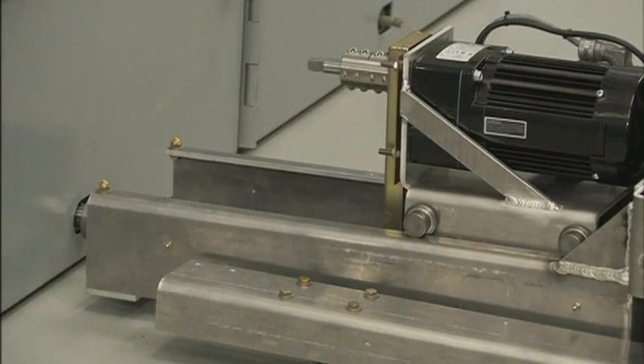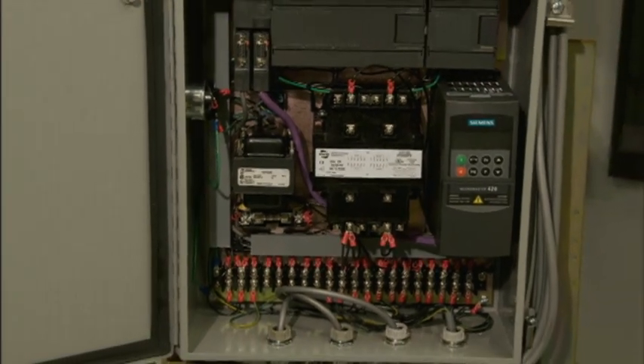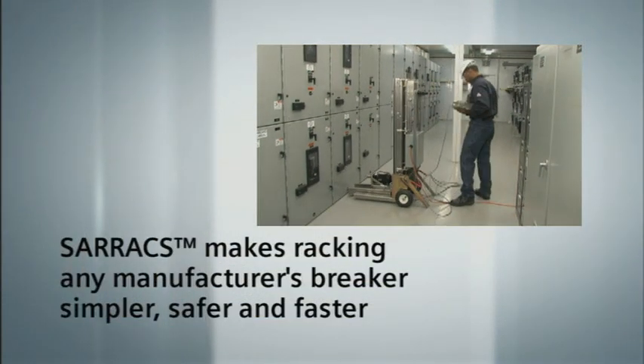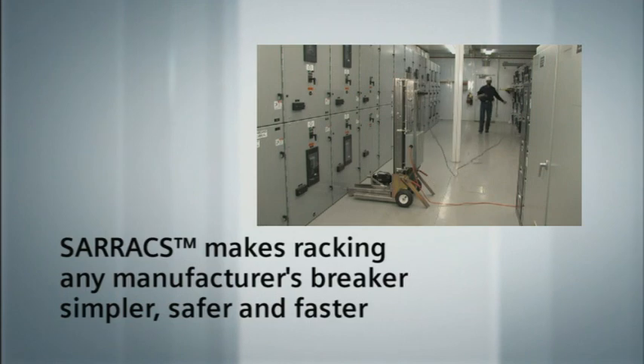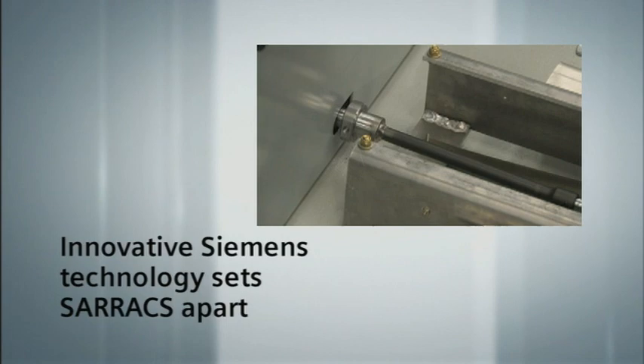SARRACS, the safety remote breaker racking system, provides increased protection for your most important assets — your personnel and your equipment. With this life-saving innovation from Siemens Industry, the operator is positioned safely outside the arc flash boundary while racking any manufacturer's breaker in or out of a live bus. Not only is safety enhanced, the need for flash suits is eliminated.